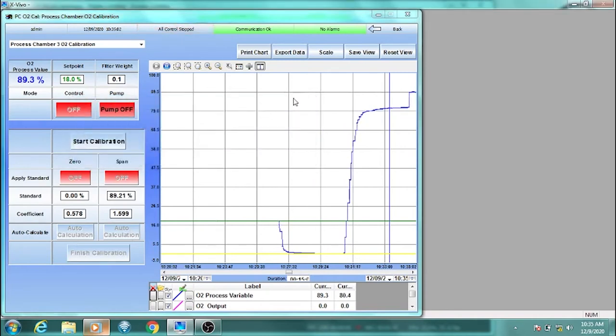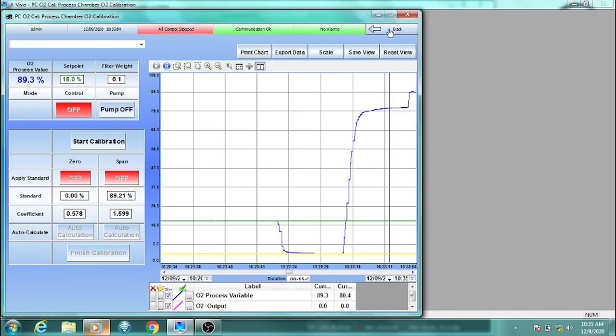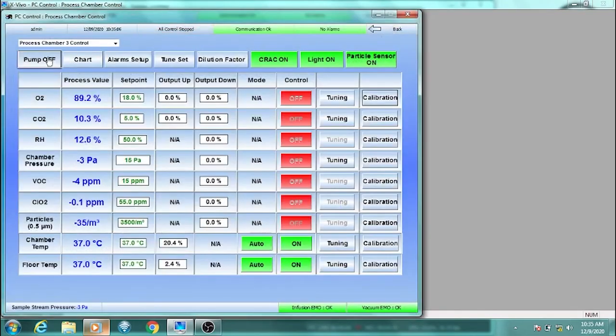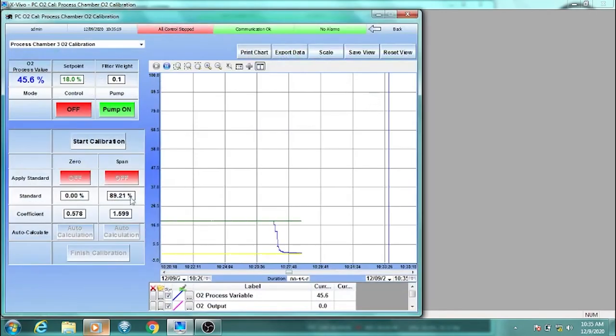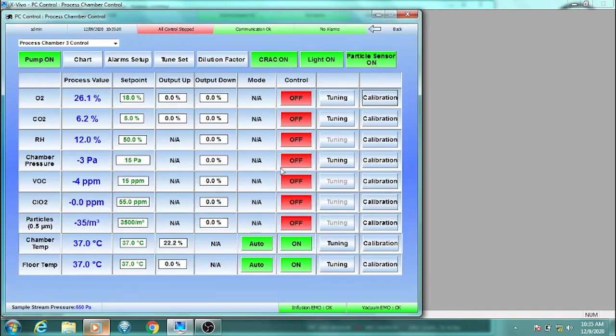Go back to the main screen of this module and turn the sample stream pump back on. Wait a minute or so for the sensors to start sampling and reading the atmosphere in this module again before turning controls back on. Write down the coefficients for the zero and span each time you check the calibration to document how much they are changing over time. Big changes in the coefficient are a sign that your oxygen sensor's health is beginning to decline. Make sure to close the span tank once finished calibrating.